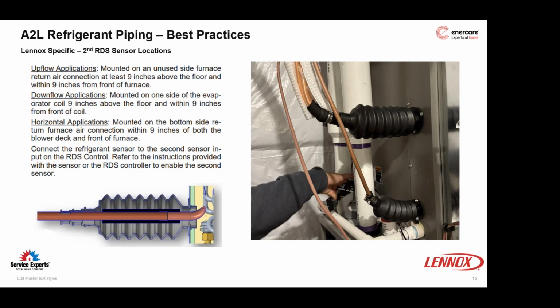Lennox's list here on the left, I'm not going to go through them, but basically they're saying within 0 to 9 inches of the back of the furnace, on the side of the furnace that doesn't have the return on it, they want you to put a sensor in there, a minimum of 9 inches off the floor, but below the burner of the furnace, install the second sensor. And the control board, you can tell it's got 1 or 2 sensors, and we'll get into the depths of how to set that up, but you can add a second sensor.